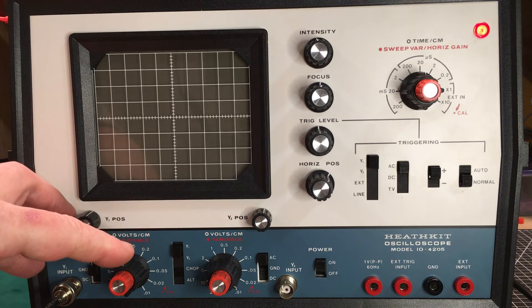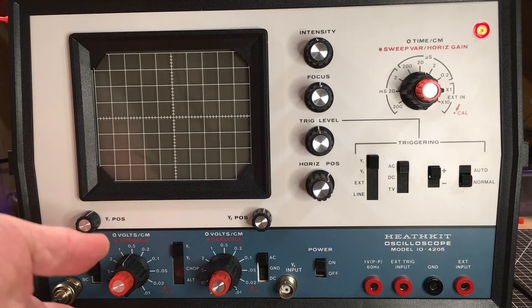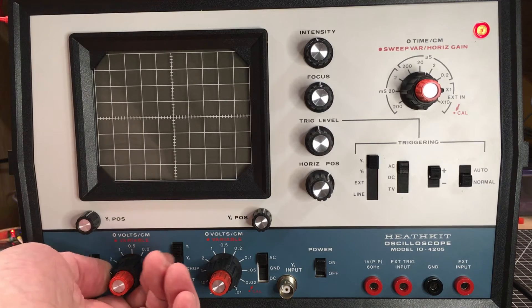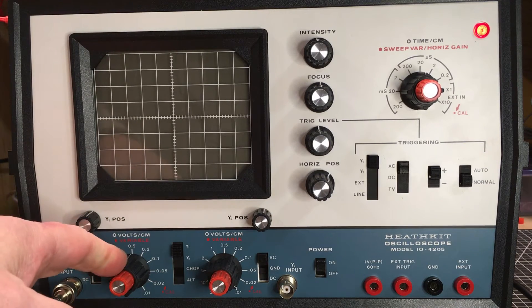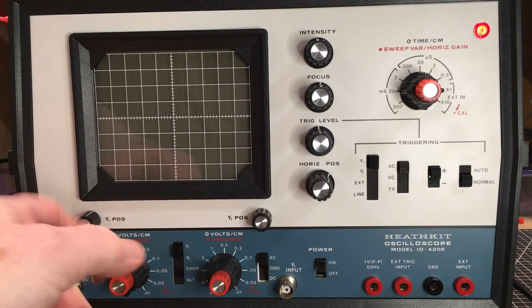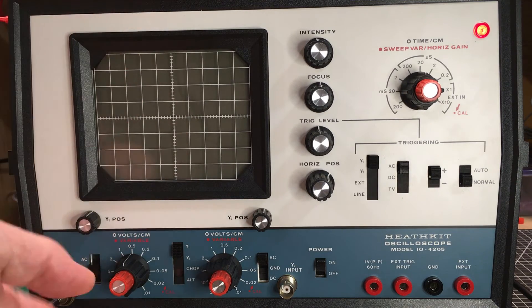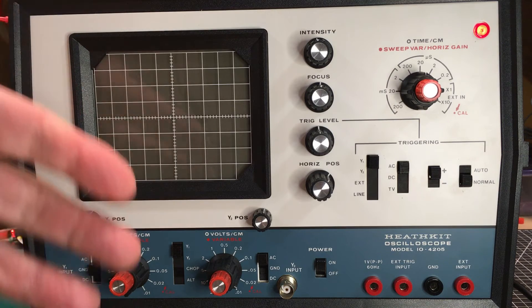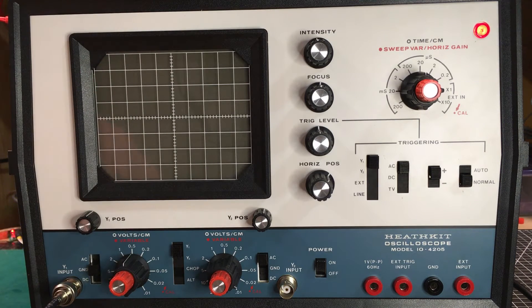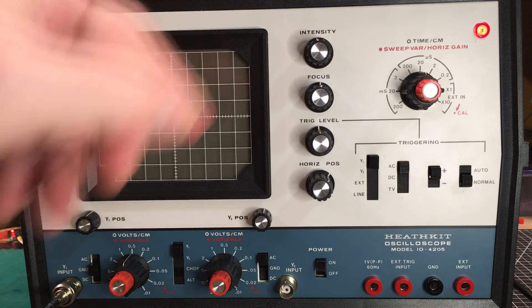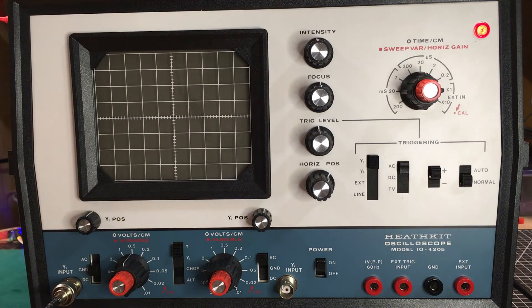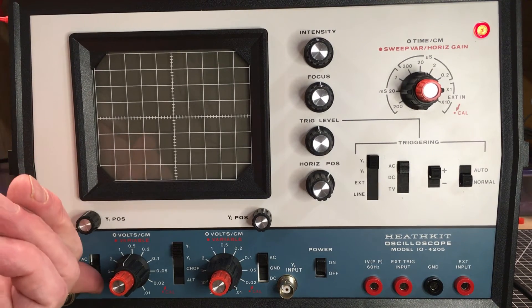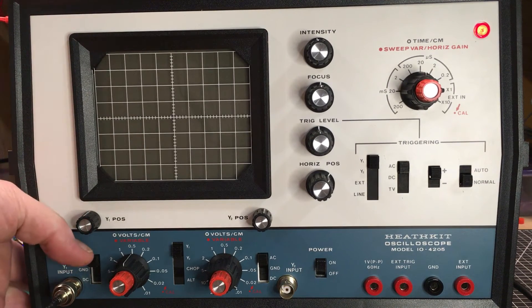Over here we have our vertical control. We can see here, this is the attenuator, so we can choose whatever amplitude that we want. This is usually graduated in volts per division. In this case, volts per centimeter. Divisions are one centimeter here. Generally speaking, if you're going to set up to look at a signal that you're not sure exactly what it's going to be, then put these dials in their middle positions and go from there. Here you have the position control here, and here you have your coupling control.